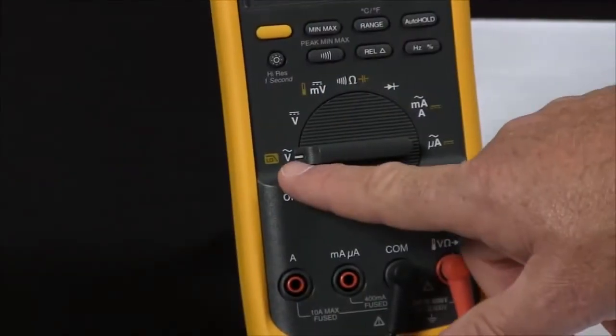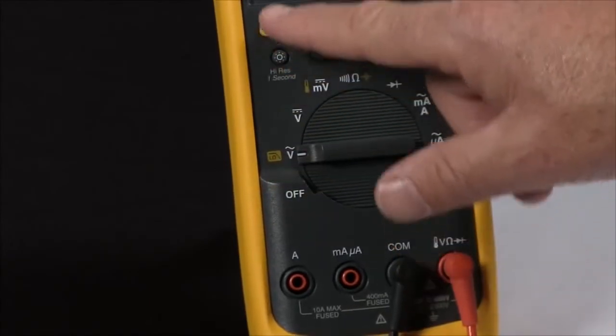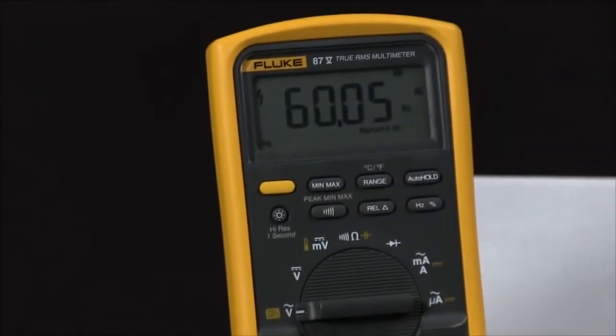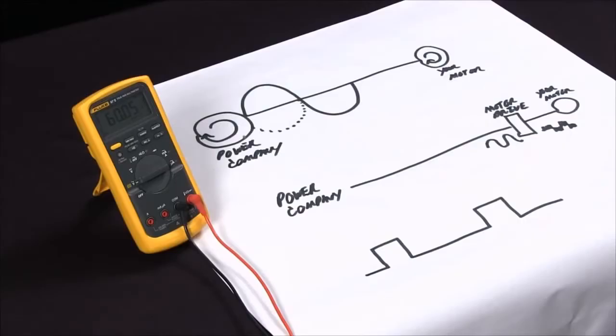If you see next to the AC volts, there's a low pass. By hitting this yellow button, what I've done is I've now converted this into a special measurement mode that will measure this pulse width modulated signal accurately, giving you the frequency. So you can see if the motor is truly at full speed at 60 Hertz, half speed at 30 Hertz, quarter speed at 15 Hertz.